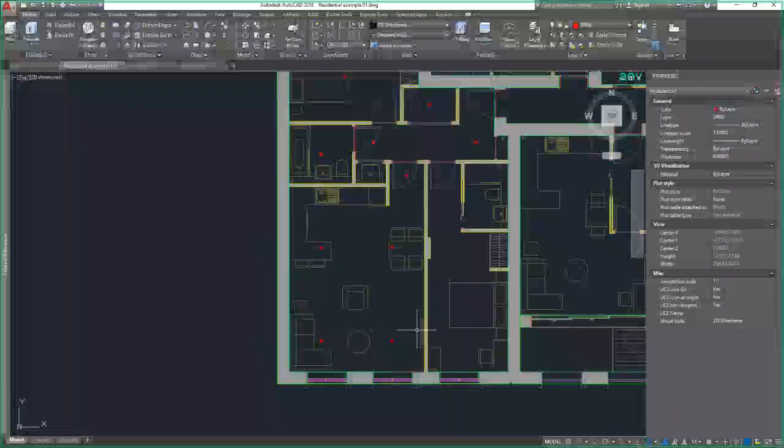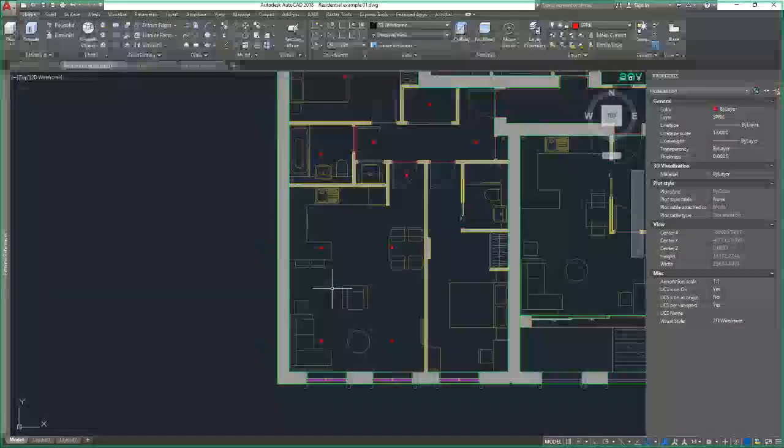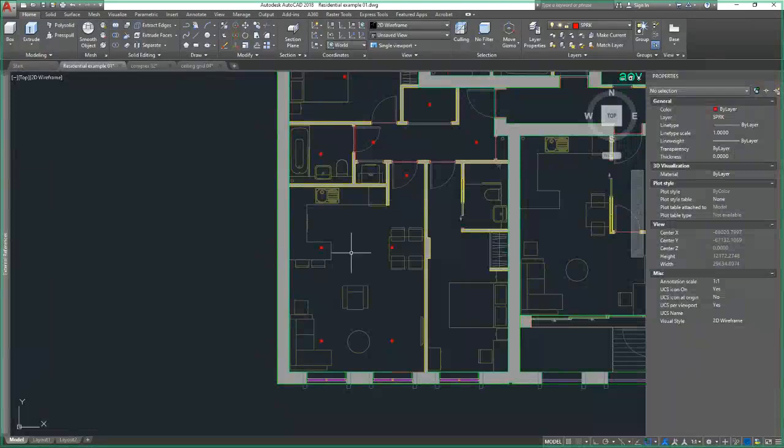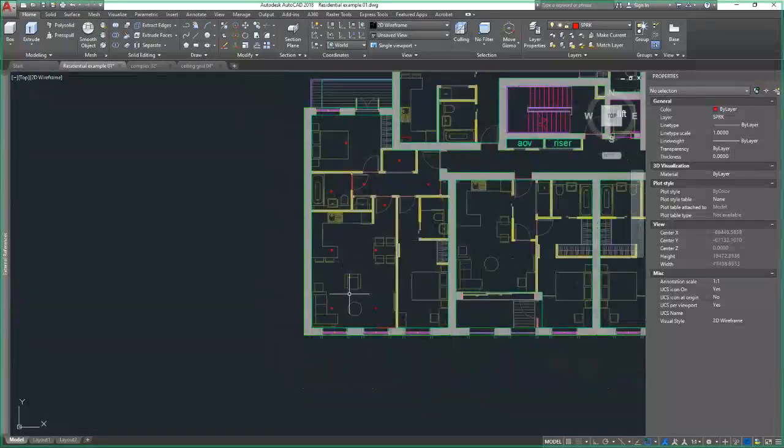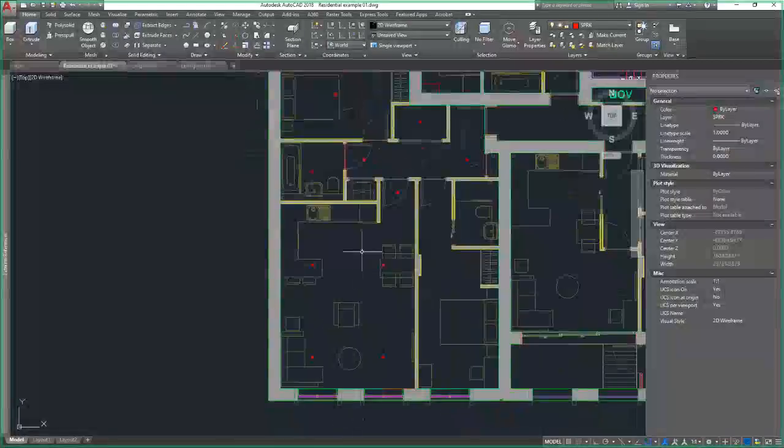So if you actually calculated the area divided by 5, we've got loads of heads in there for the size of the room. It's just the way the cookie crumbles, really, in terms of the size and particular shape of the room, which just meant that it was unavoidable, I think, to have 5 heads within that space. So I'll leave it there as going through it. That's hopefully given you a good starting point in terms of how we actually use that information on the minimum and maximum distances in a practical situation here with our residential setup.